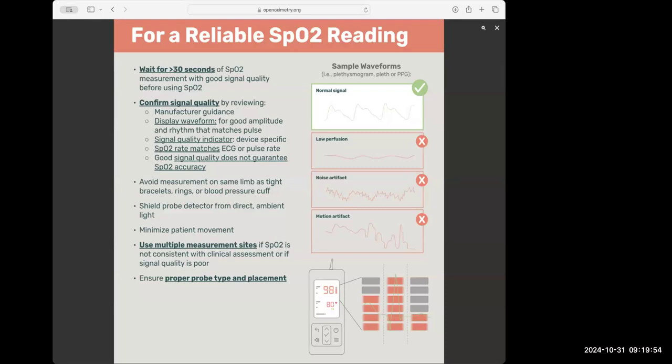Are you asking about whether the alarm signals are effective at communicating and functioning as a risk control measure? Yes, but specific to signal quality. Well, all alarms are supposed to be, and I use this term, validated. But does signal quality fall into that? It will now, yes. All communication to the user, signal quality is a form of alerting the user of a hazardous situation, and that's basically the definition of an alarm.